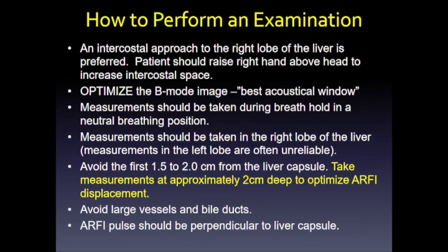The examination is performed using an intercostal approach to the right lobe of the liver. Substernal approaches or imaging the left lobe often require extra pressure and probe angulation away from perpendicular to the liver capsule, causing problems. We optimize the B-mode image — which indicates the best acoustical window — ensuring no shadowing, so we get a stronger ARFI pulse, stronger shear waves, and better tracking. A poor B-mode image means we cannot track shear waves.